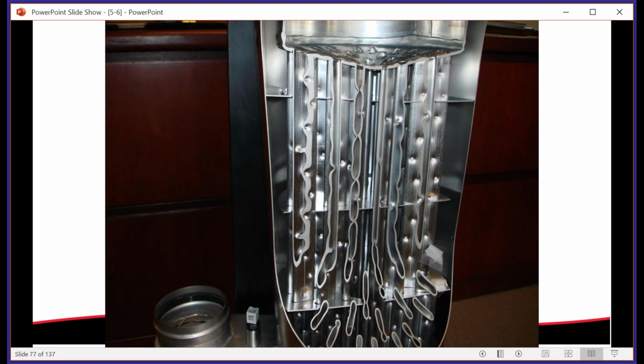Here's a nice cutaway. Again, this is a flame tube. We have those dimples, you can see those clearly. Again, the purpose of the dimples is to maximize our efficiency for heat exchange. Okay? We don't want to just blow the flame in and send it on its way. We want to kind of slow it down a little bit, create some turbulence, really let that water that's backing up these heat exchanger tubes exchange that energy. Okay, again, this all goes down to efficiency.